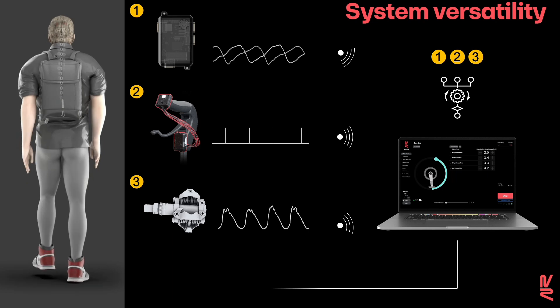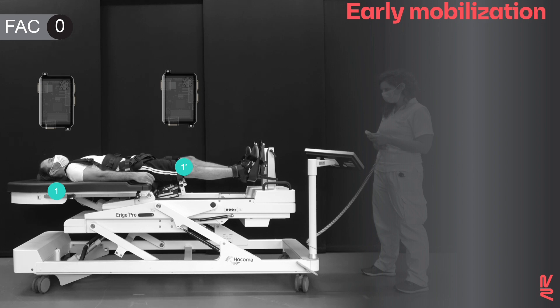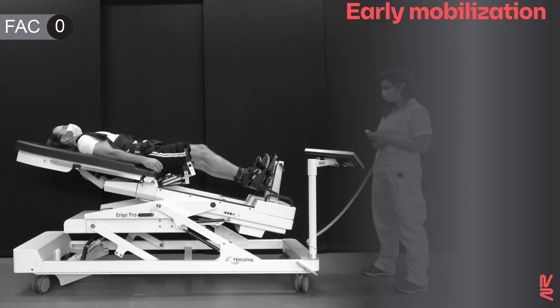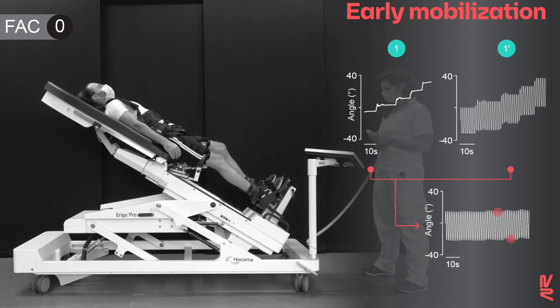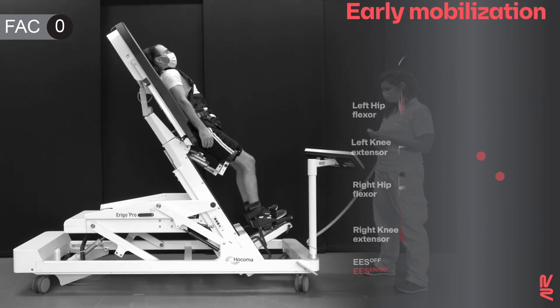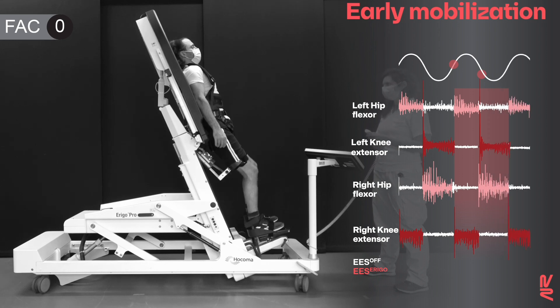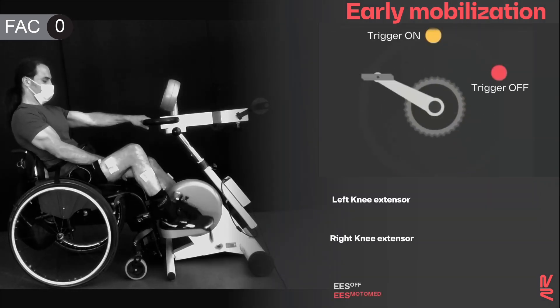The intended movements and device operations are detected based on external sensors to ensure time synchronization of the stimulation with the robotic actuation. Erigo allows early, graded, and safe mobilization of the lower limbs. We placed motion sensors on the frame and limb actuator of the robotic system and merged the signals from both sensors to ensure stability of stepping detection algorithms regardless of body orientation and speed. The stimulation promoted robust activities of the otherwise silent muscles.